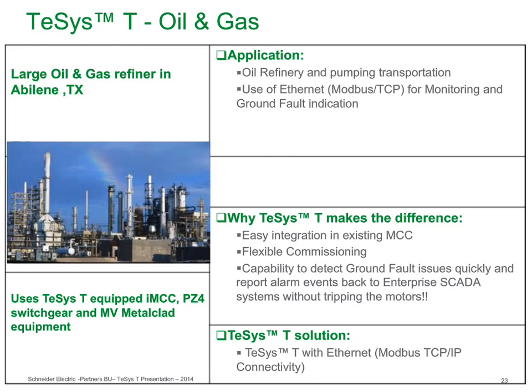And not all devices can do that. And so they actually use mild ground faults with an alarm to basically be indications of where they had potential problems in either wiring that might be affected by vibration or corrosion or other sources of where the ground fault actually helped detect. And they actually tied this in with their SCADA systems to basically allow them to have full diagnostics using the data input coming from the TeSys T. So this was a big savings for them.